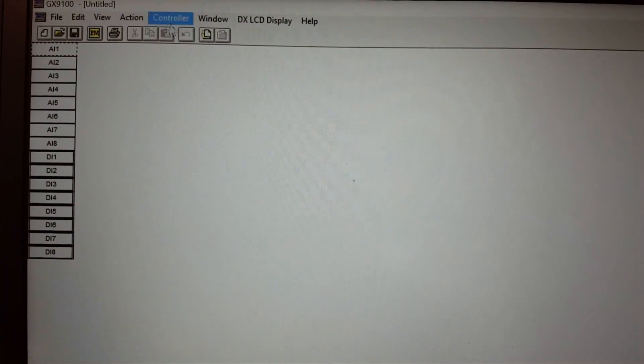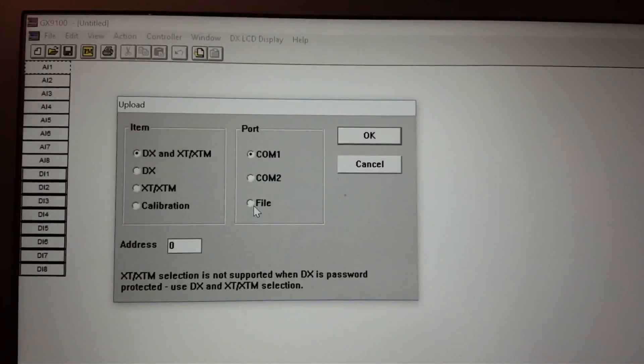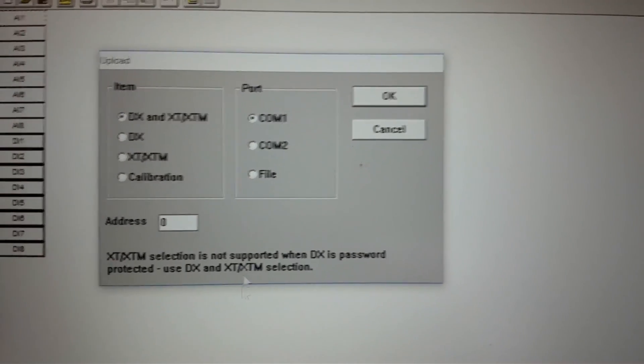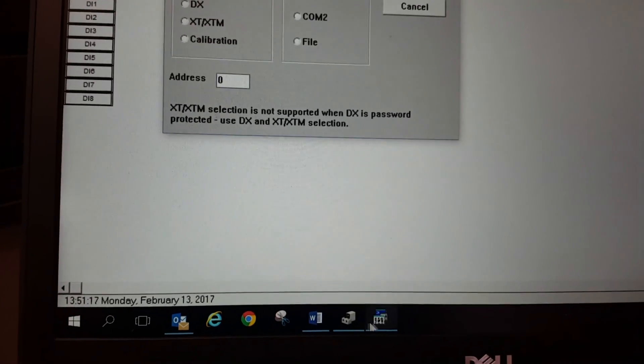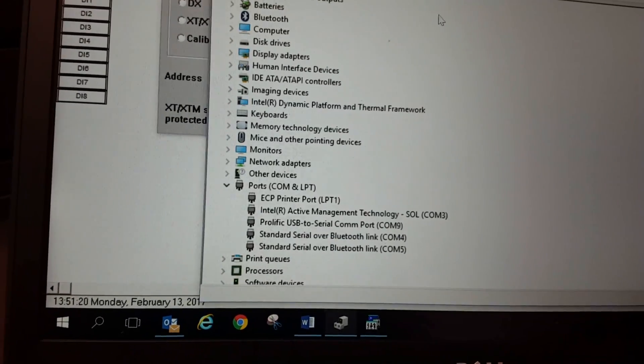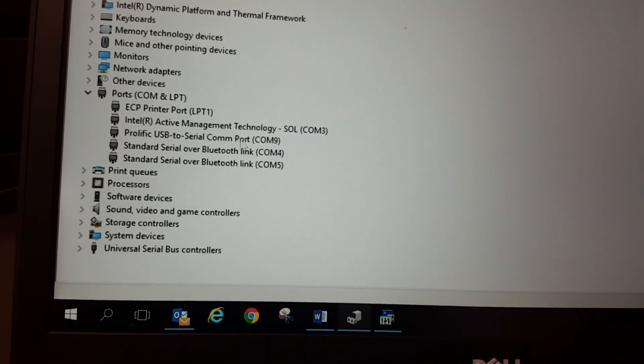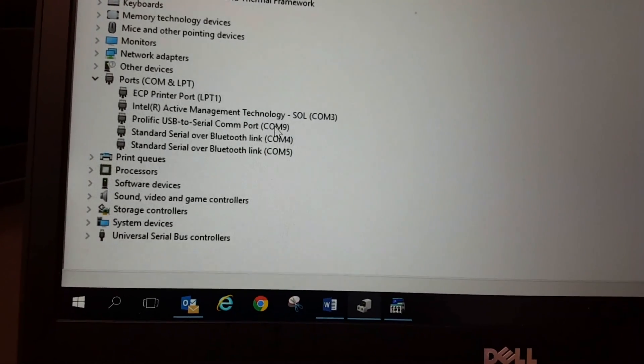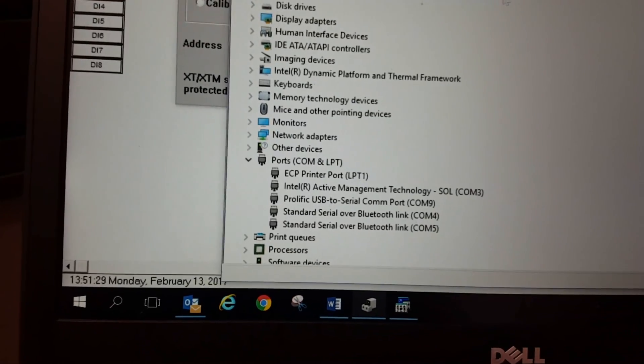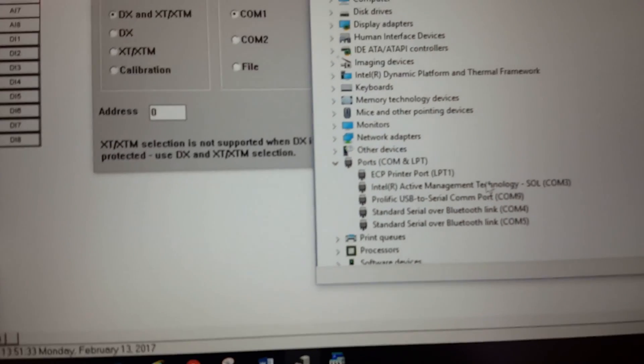If you look at the software — if I simply go to upload or download — you can see here that I only have a couple of options: COM port 1 or COM port 2. I do not have any others. If you try to upload or download through your device and you do not have the correct COM port selected, it will give you a communication error. This is something that I learned from experience.